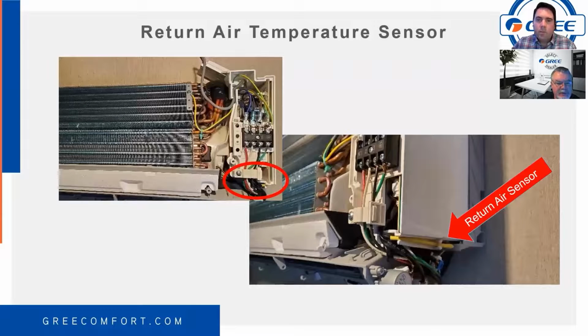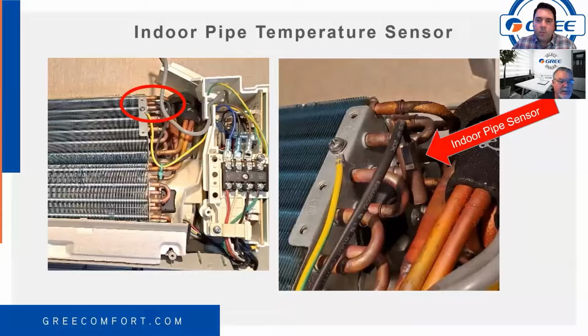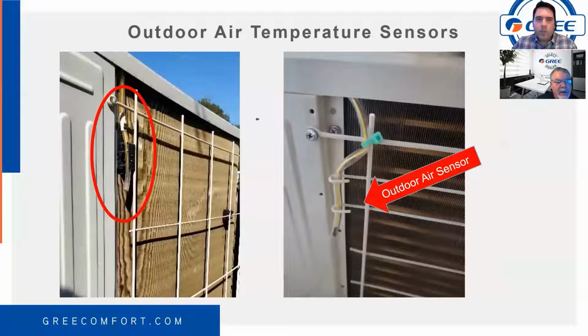Return air temperature sensor is located usually down here in the bottom right. You see it located there, the yellow sensor. And then the indoor pipe sensor is up here on the evaporator, and there's a little close-up shot. That sensor during heat mode is monitoring how hot the indoor coil gets. So if it's not able to remove enough heat, then it could throw the E1 error code as well, because it's sensing that it is over temperature. Yeah, and it's determining the fan speed. Yes. And it also sends a signal to the control module with other sensor inputs to control the flow of refrigerant through the EEV.